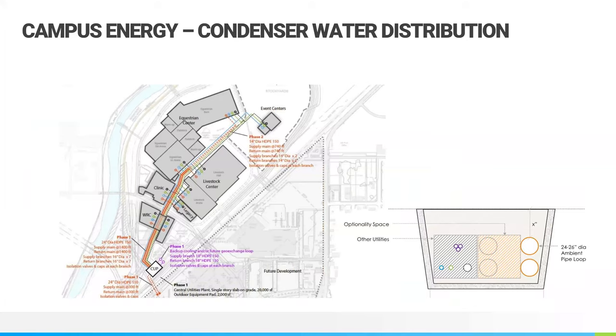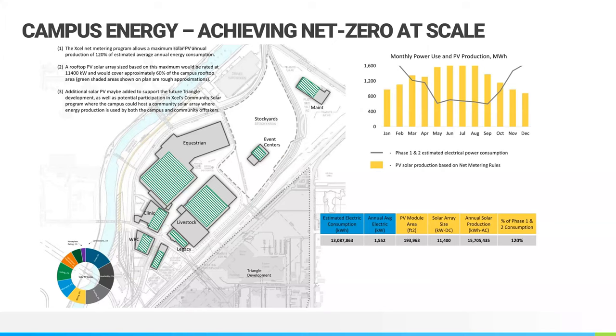Kind of get an idea of what they were building out, total size wise. You've got all the different buildings that connect in. There you can see at the bottom, the CUP is the central utility plant. From there, the ambient water is distributed out to each building. And again, each building connects to that and it provides heating and cooling for itself. And again, achieving that net zero at scale, they looked at the total power consumption on an annual basis, and looked at exactly how much solar they could do based on the Xcel net metering rules. And as you can see, they were able to really get that net zero power consumption possibility with the amount of solar that they get on the rooftops.